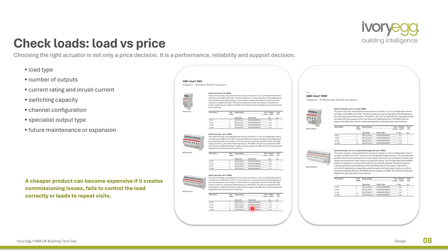Of course you can choose the best one, but the best one is very expensive. So you should know the load type, number of outputs, current rating, and inrush current - very important for LED types - as well as switching capacity, channel configuration, which matters when you use a combo switch, specialist output type, whether you need the energy function, and future maintenance or expansion.